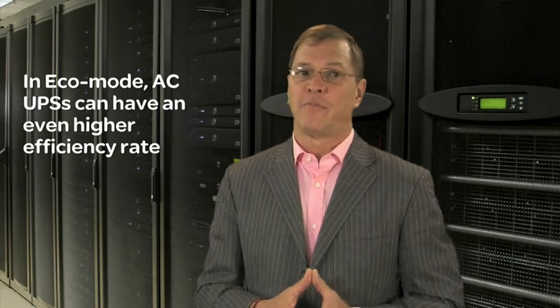Data centers used to be as low as 85, even 80% efficient on the power path side. But today, using modern eco mode UPSs, the AC system can actually be more efficient than a DC system, because the AC UPS, when used in eco mode, can achieve 98.5% to 99%. And since in a tier three system only half of the power goes through that device and half goes direct, 98.5% becomes more like 99.4% as an overall system efficiency from the UPS standpoint. When combined with a few other transformers and so on, we're still back down in the 98% kind of range. Pretty hard to beat that by any significant measure using an alternative approach.